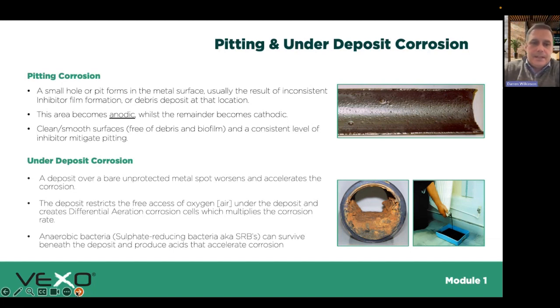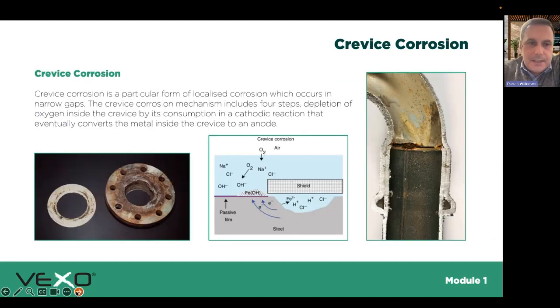Some bacteria, particularly anaerobic bacteria, sulfate reducing bacteria, can quite easily thrive underneath those deposits, and as part of their byproduct, even iron bacteria, they will actually produce acids, and those acids can then cause pinholing. So if you have horizontal pipe work and you start seeing pinholing, chances are you've had deposits laid down, and it's generally flow rate related.